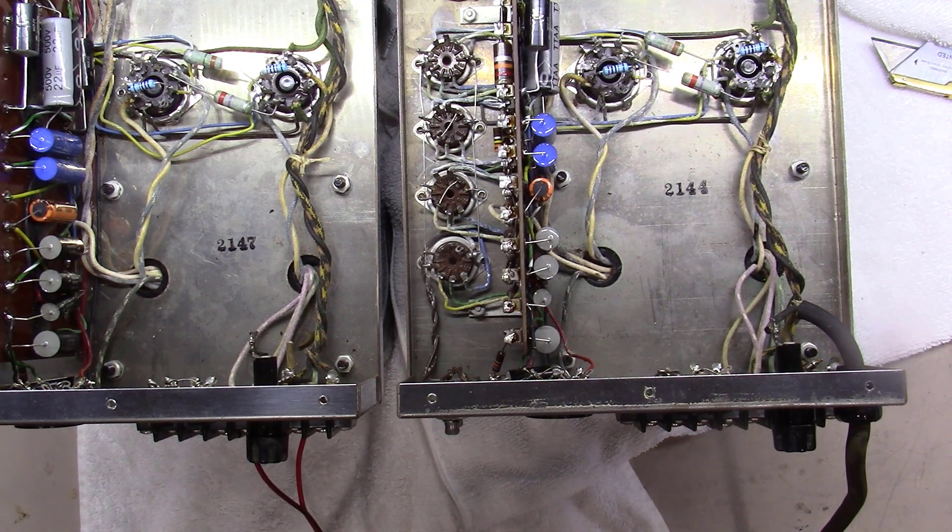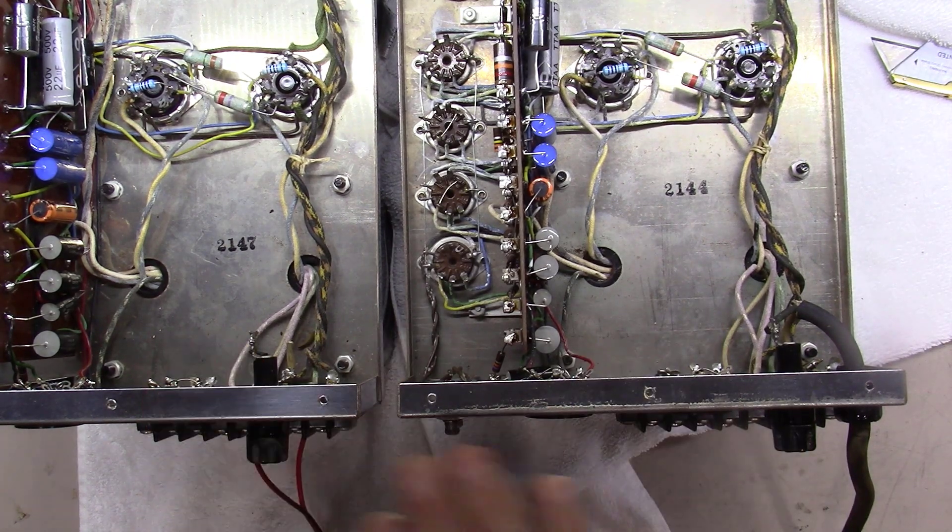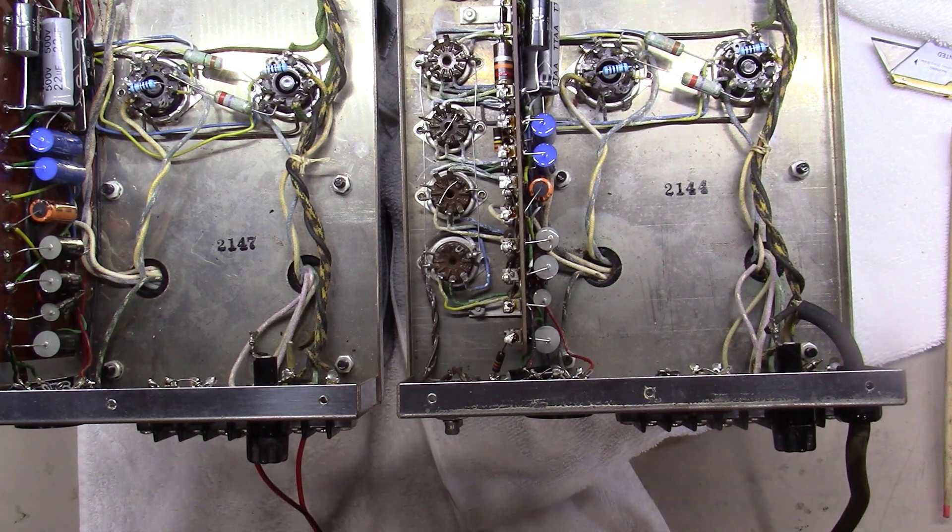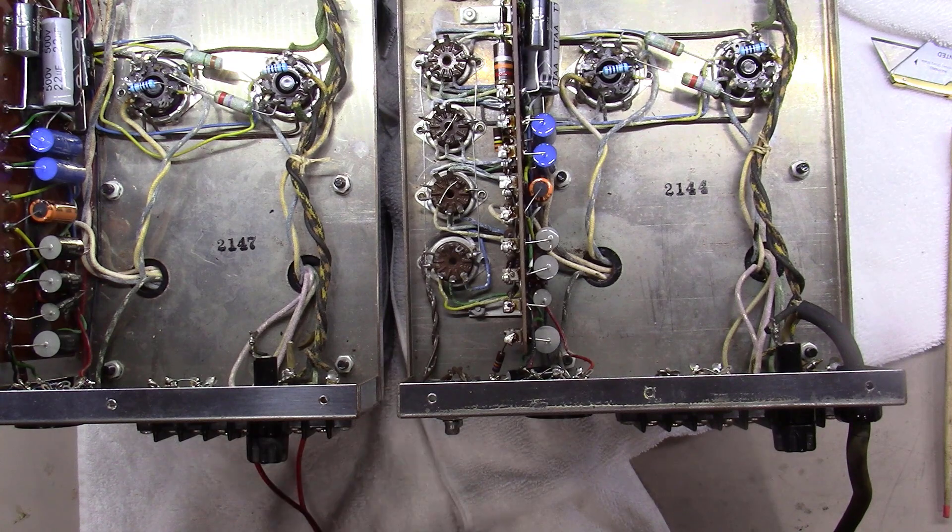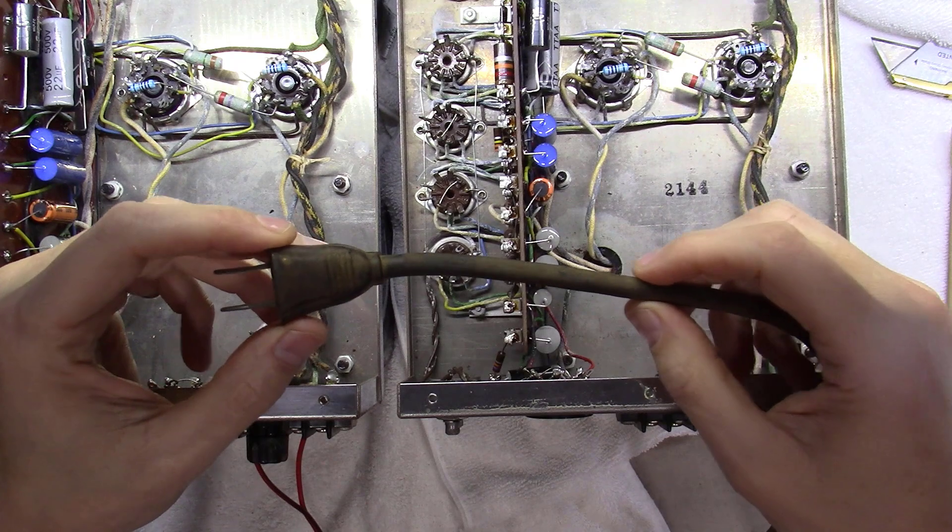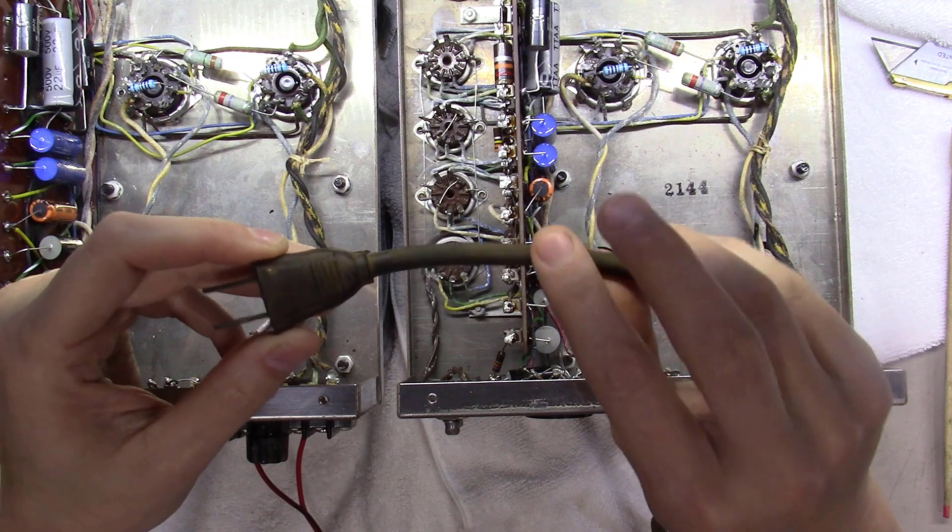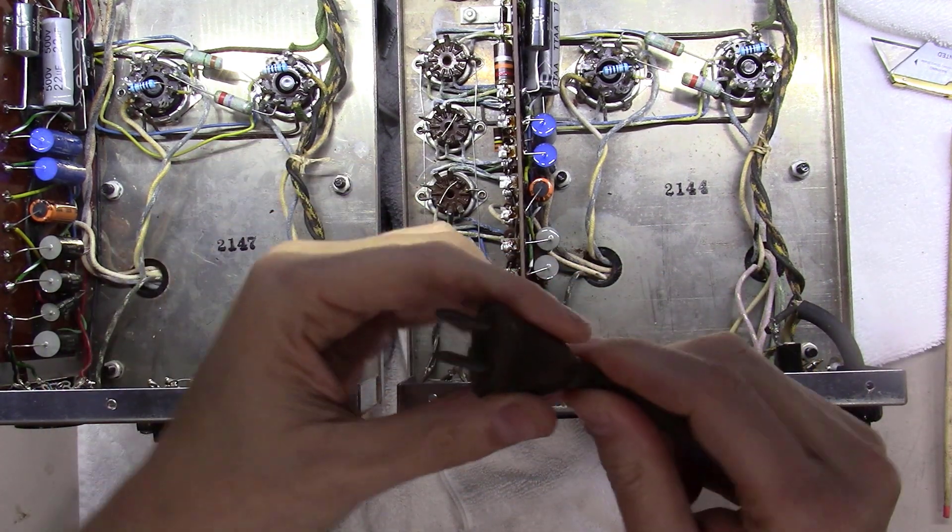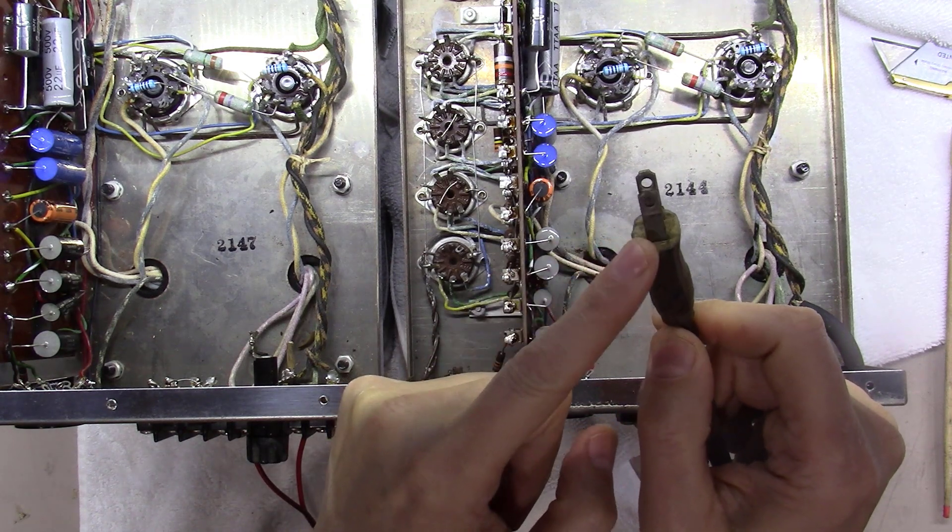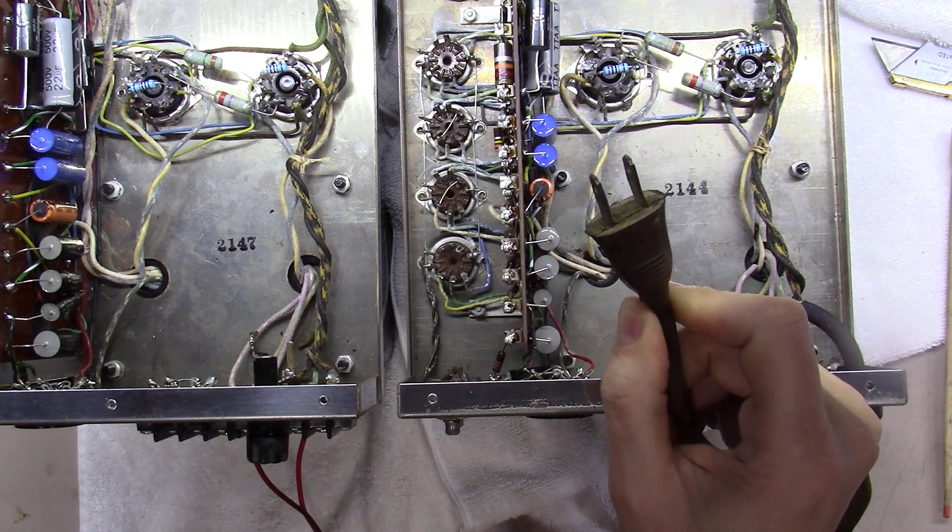In this case these are MC-30s, but the same would hold true for older MC-60s, MC-75s, and likely other units. The scenario is these older cords have this larger size round body with a little bit of ribbing on it. They have a rounded head, but most importantly they have a two pronged cord that is non-polarized. One blade is not larger than the other blade.